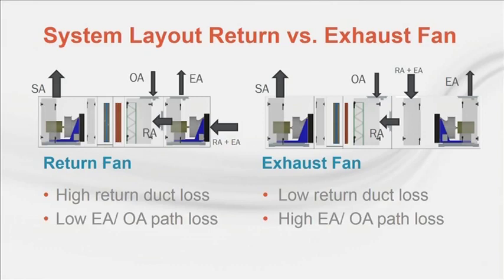Care also needs to be taken using return fan systems if there is a high loss on the outside air path or exhaust path. This would be the case if the unit is located in the building where there are long duct runs to the outside air intake or exhaust outlet. This is also the case when there is exhaust energy recovery. Here, a return fan system will often require more fan power than an exhaust fan layout.